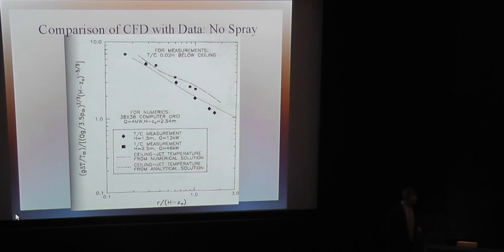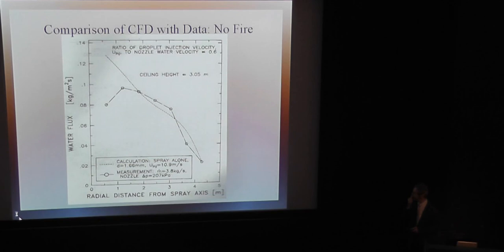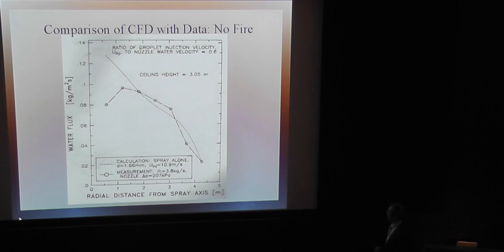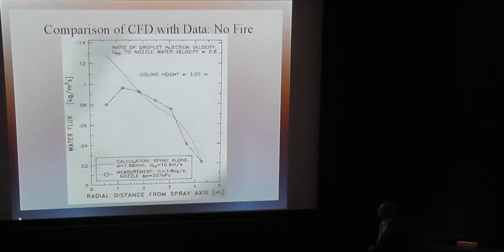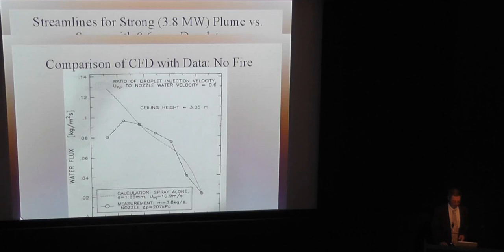We also did some computations where there was no fire at all — just the spray alone. We wanted to look at the variation of water flux at the floor level, how it varied with distance from the axis of the spray. These are the calculations, and these are the measurements that were made of how the water flux varied with radius. At least that's something we attempted to do to see how reliable the calculation was.